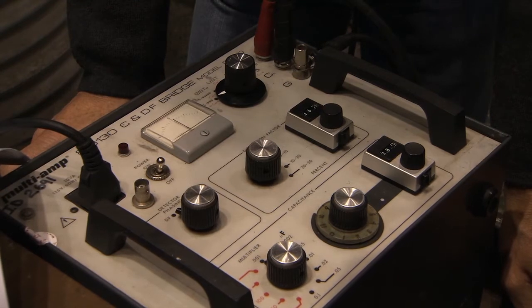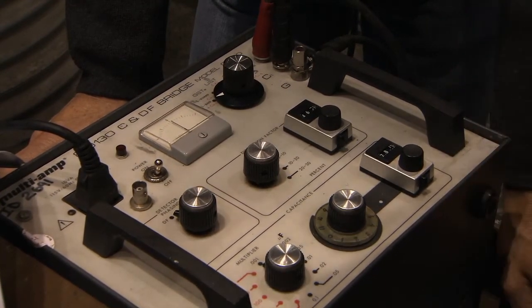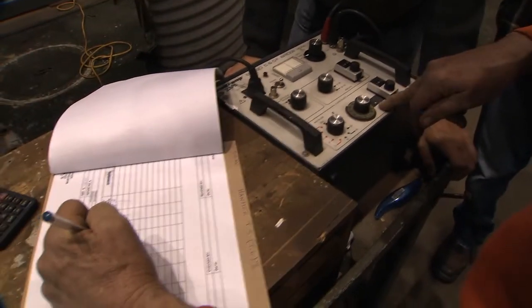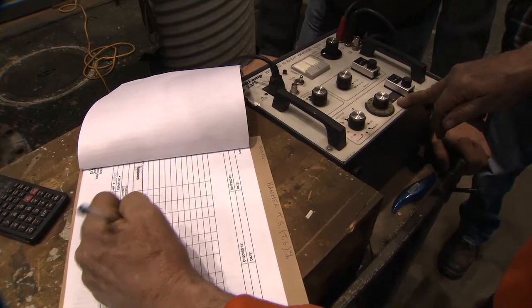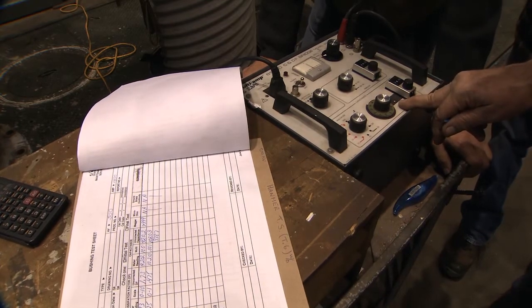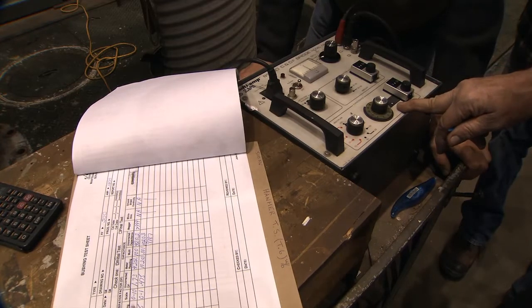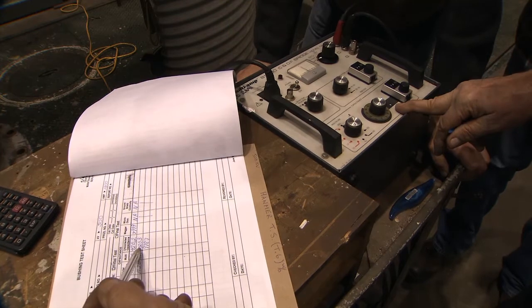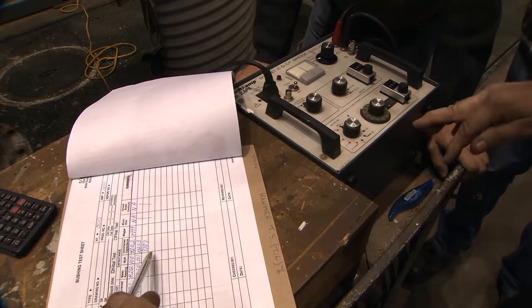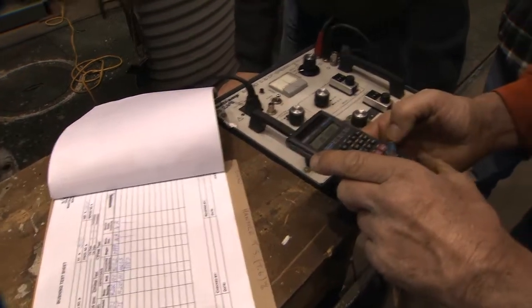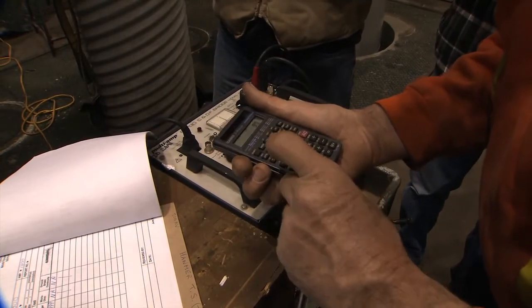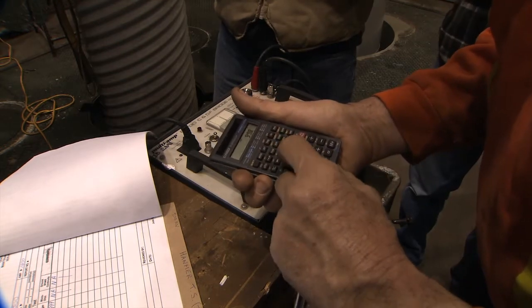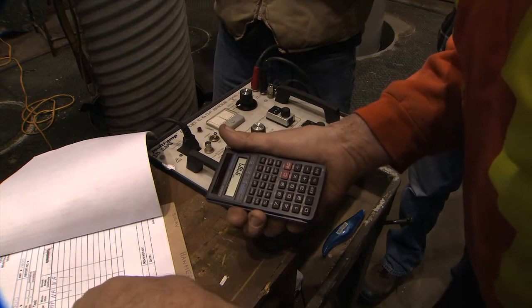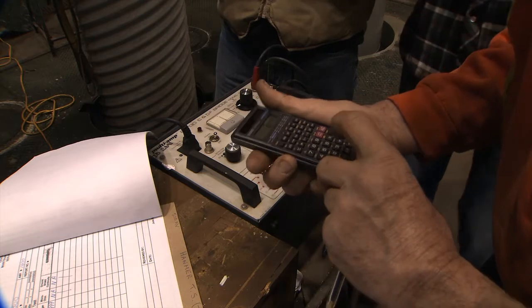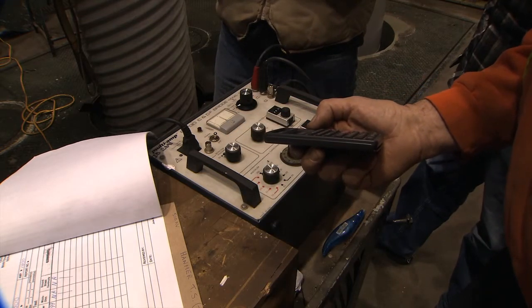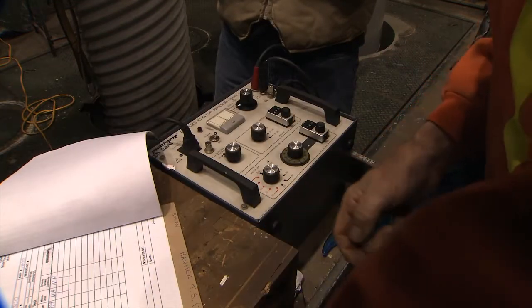So this is what you would do. You would put 10,203. And this one here will be 9,787. And if you take your C1 and your C2 and add the two together, you will come out with your C1 plus C2 test. See? Within a few picofarads. So just to show you, you're 500 out. So if you do 9787 plus 420, equals 10207. You had 10203. Okay. See? Wow, that's pretty good. So that's your actual test there.